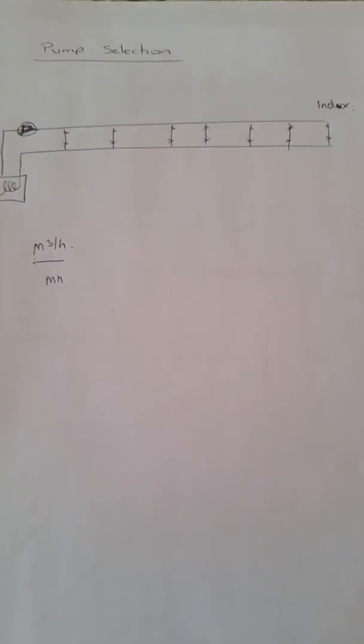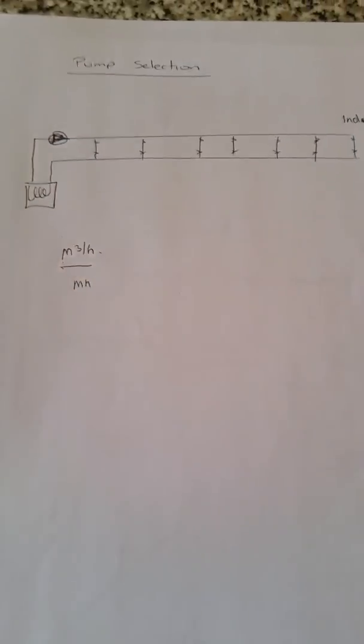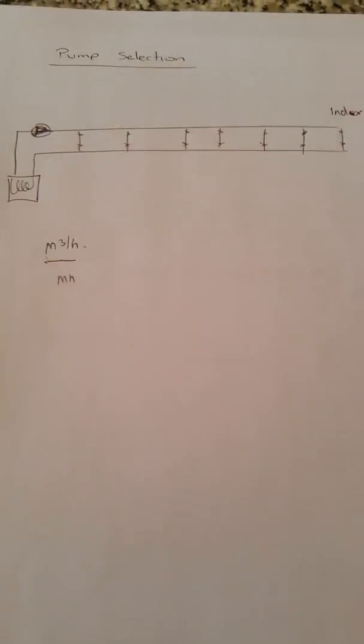And for this reason, lots of people are saying, well, I've never had a problem, I've always managed to get my radiators to work, and I don't think hydraulic separation is necessary. Well, I'm sorry, but they're often wrong. And in fact, they did need hydraulic separation. All they've done is balance the system and reduce the output of their radiators.